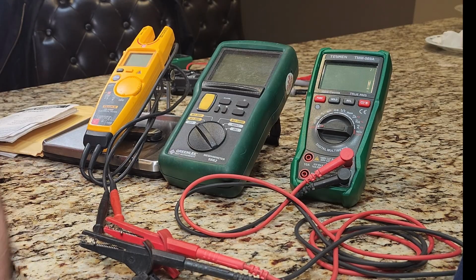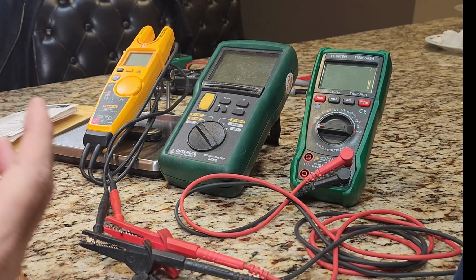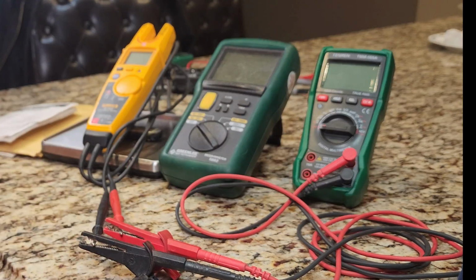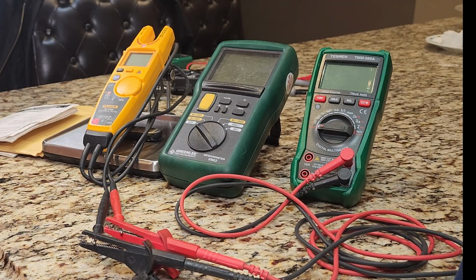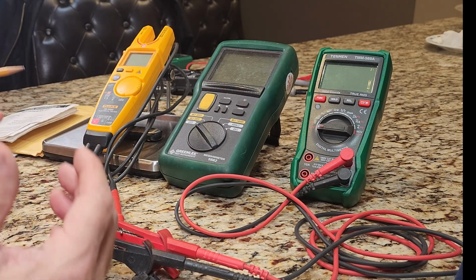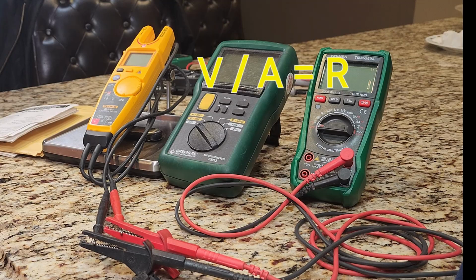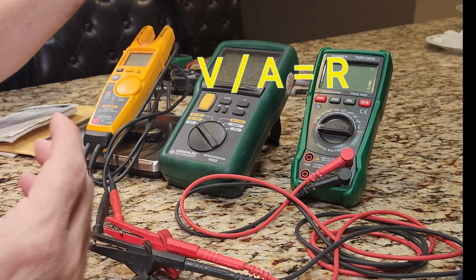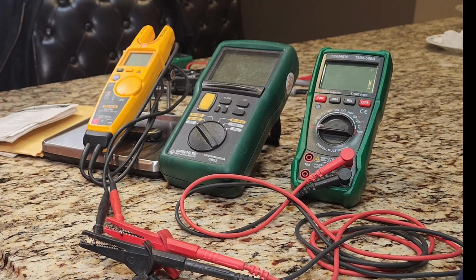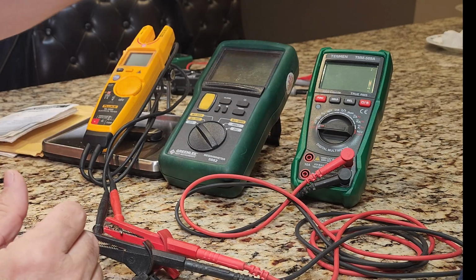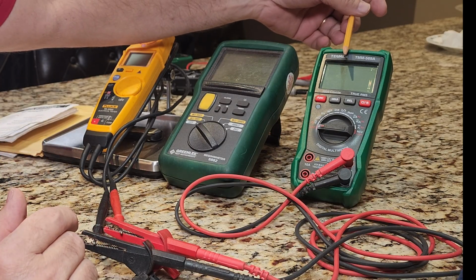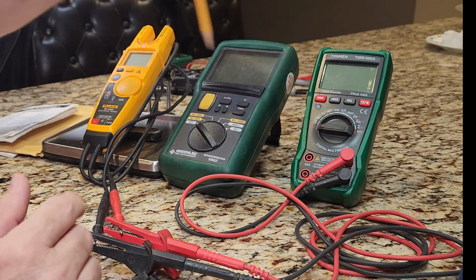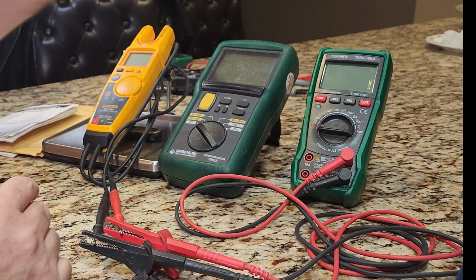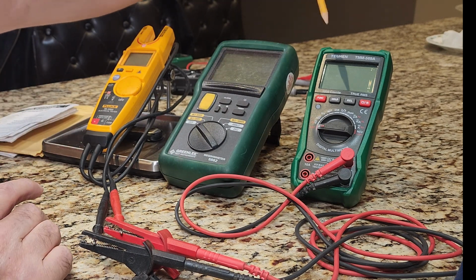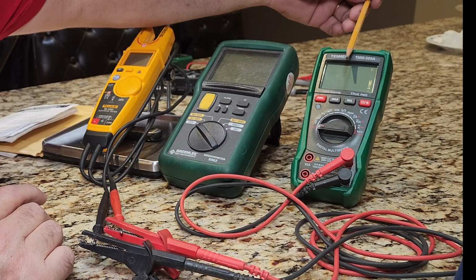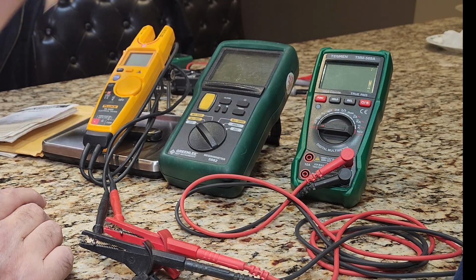Okay. So the first thing is, how do we measure resistance, right? If we go to Ohm's law, Ohm's law says that if we take voltage divided by current, that's resistance. So basically, any meter that's measuring resistance has to have its own voltage source. It takes the 9 volts that's inside the meter, adds some capacitors and steps up the voltage, and we're going to test that. And that's really the difference: how much power this could put out to do a test versus a megohmmeter.